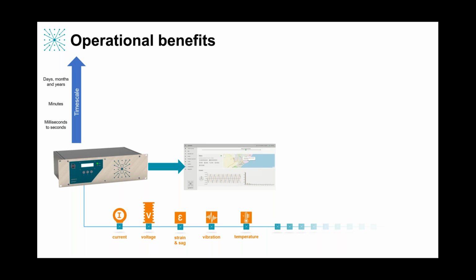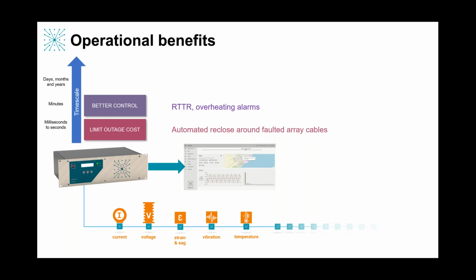And that can be used in three different ways. And we normally talk about this across three different time scales. So when we're thinking about protection applications, we're operating within 2 milliseconds to find a fault, isolate it, and get back into production as fast as possible. So at a very simple level, our technology is used for digital substations around the world where you want to limit the cost of an outage. And it's about automatically reclosing around a faulted cable in an array, and then keeping production up as high as possible and keeping outage as low as possible.